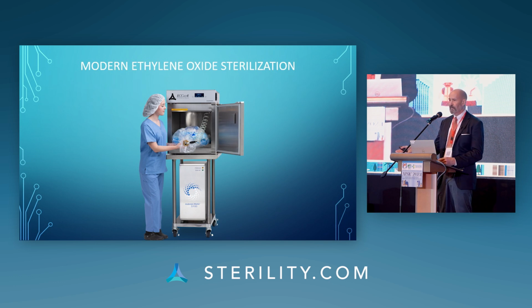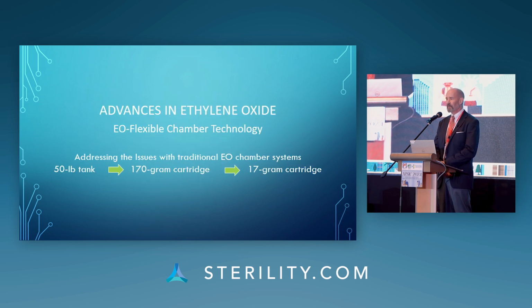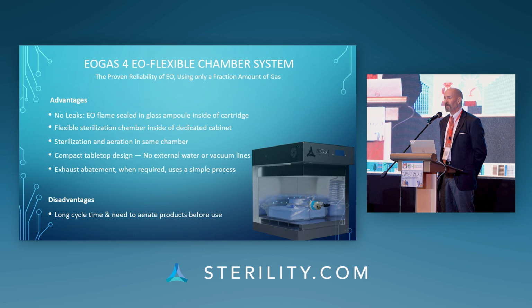And I'll start off with this slide. We have gone from 50-lb tanks to 170-gram cartridges. Today, we have cartridges that are only 17 grams. So you have had a steady decrease in the amount of ethylene oxide necessary to sterilize. The advantages of flexible chamber ethylene oxide address many of the traditional problems with the ethylene oxide systems that many of you are familiar with.